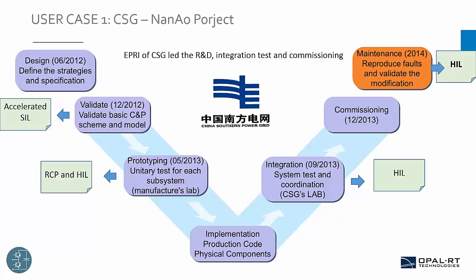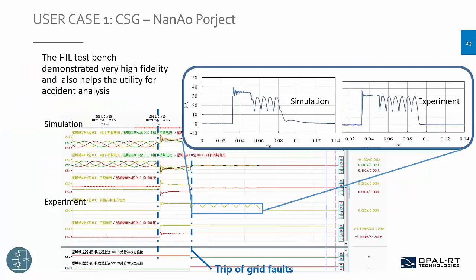So it becomes a very valuable asset for maintenance, because the utility or the owner of the MMC HVDC can connect a replica of the controller to the validated HIL test bench, on which they can reproduce an accident from the operation. And they can also optimize the protection algorithm based on the incident.